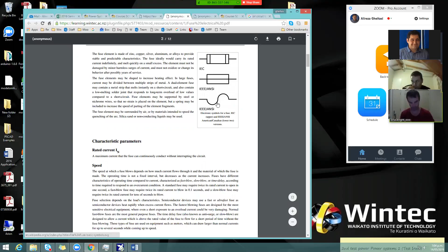To rate fuses, we need to know the nominal current, IN, and also speed. Speed is important because for a motor you need to allow more time compared to a situation like lighting.